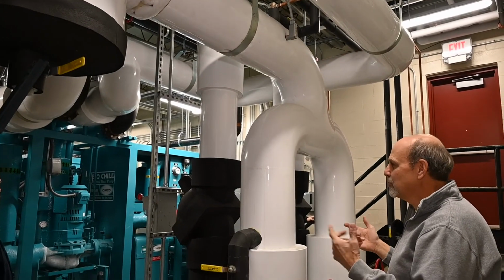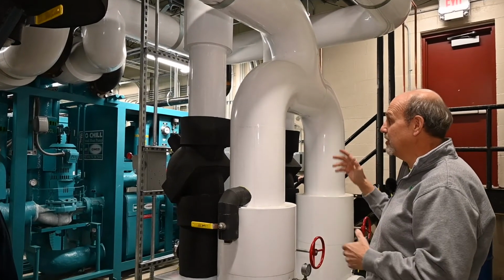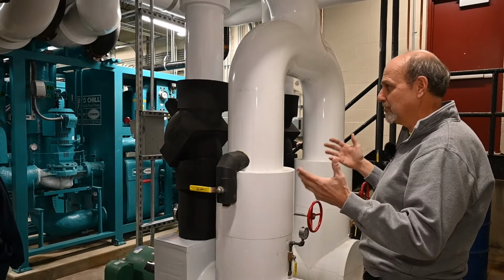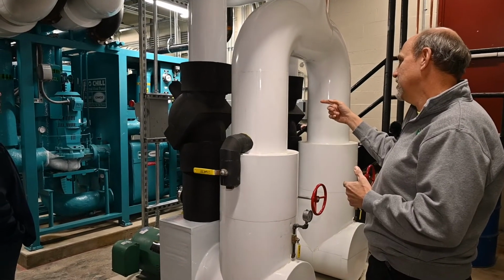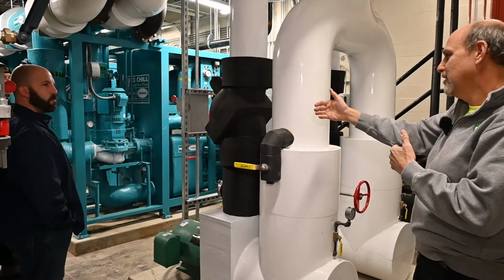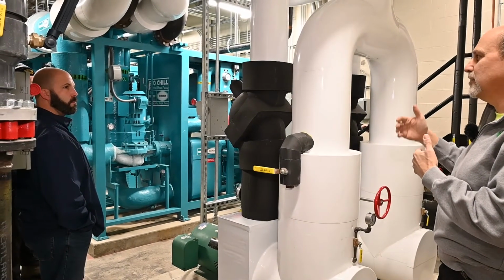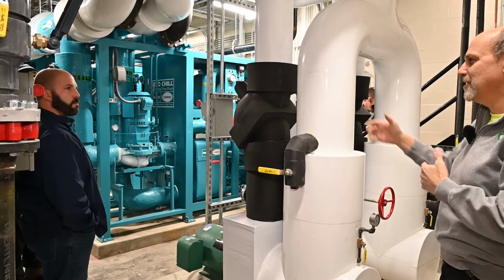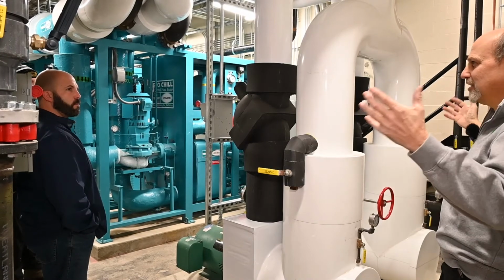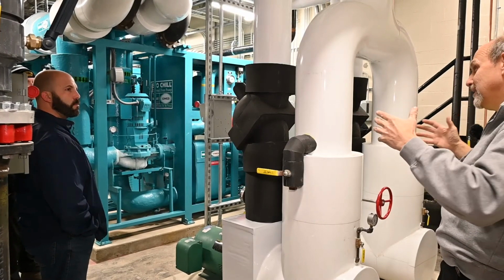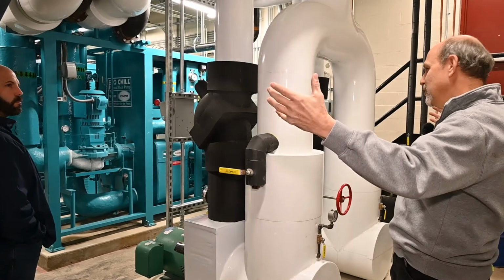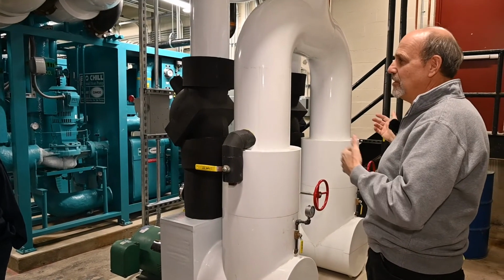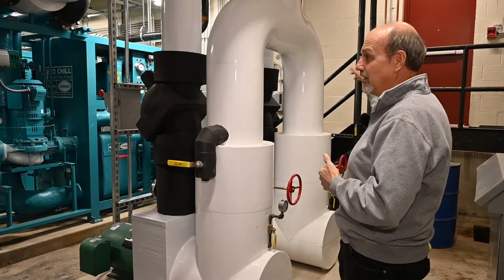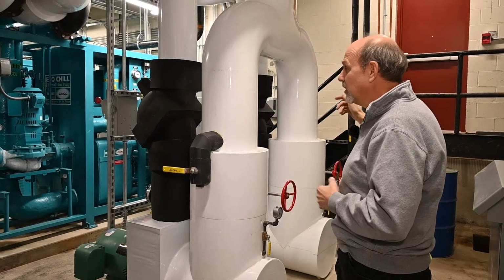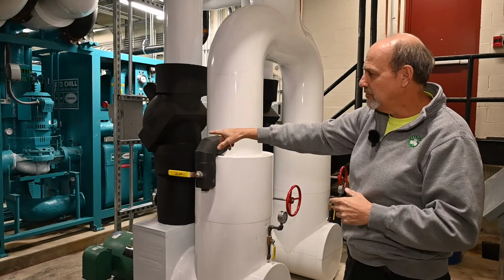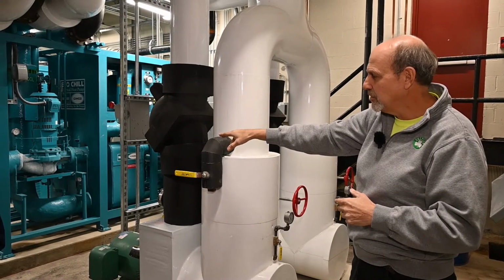There's also a refrigerant recovery system in here in the event that one of these chillers should rupture and there's Freon. The good thing about these is that they're 3 individual chillers, so if they should all fail at the same time and relieve refrigerant, you still have enough room volume here that the refrigerant would disperse itself within the room. But as a safety measure and a code requirement, we still have to put in a refrigerant recovery system, or exhaust system, if you will. So we've installed a sensor at the bottom, the base of chiller number 2.